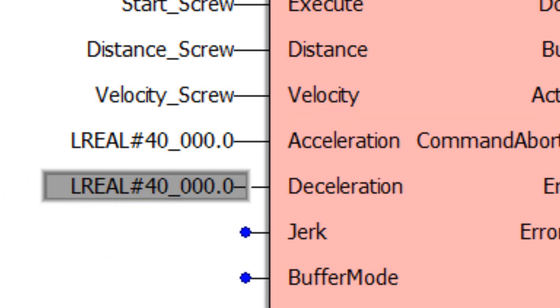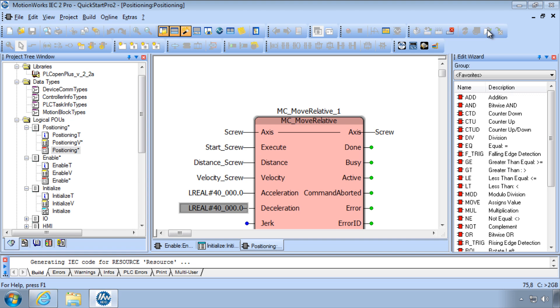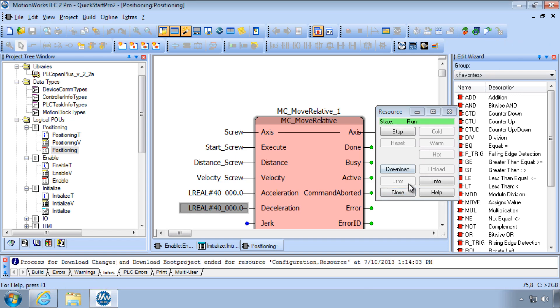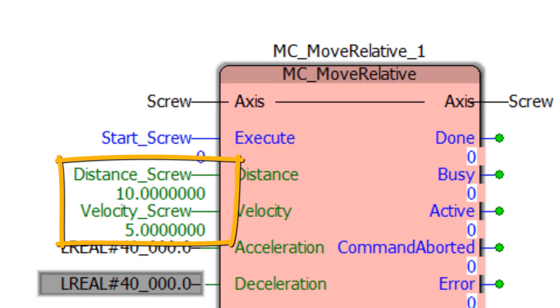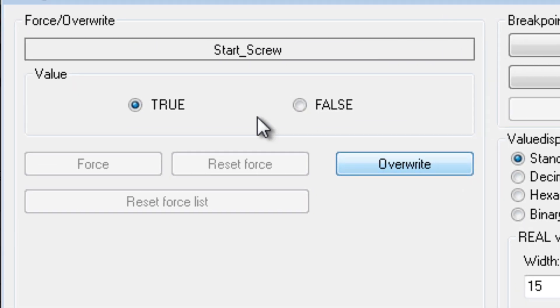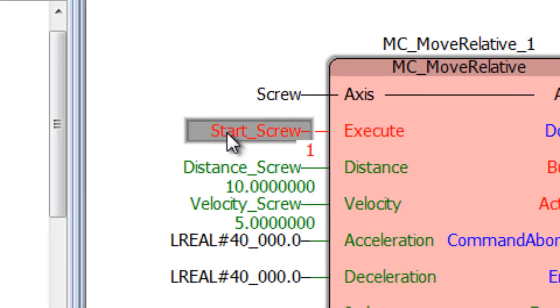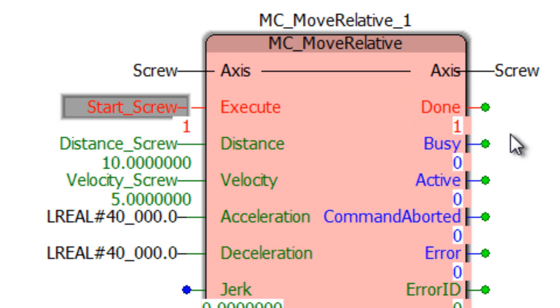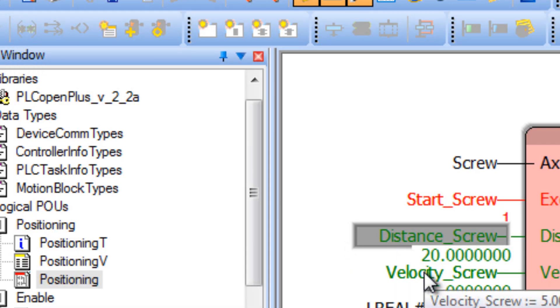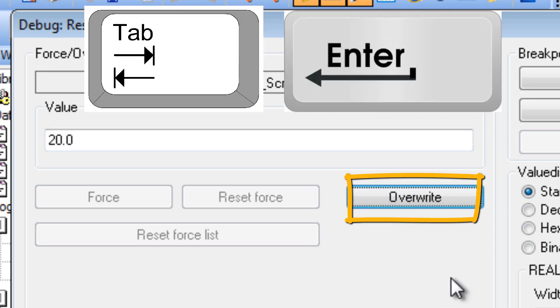Leave the other inputs blank and download changes — there were no errors. In debug mode the values for distance and velocity have loaded. To start motion, open the execute variable by double-clicking on the variable name, select true, and click overwrite. The motor moves and the done output becomes true. To simulate variable data entered by the operator through the HMI — say for distance or velocity — double-click the variable, type in another value such as 20.0, and likewise for velocity. The decimal point is also important here. Then click overwrite, and the block can now be run with these updated values.